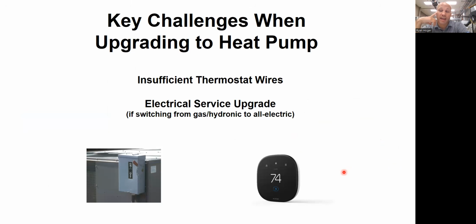But if it was a packaged rooftop unit with gas, I'm going to get rid of the gas and replace it with a heat pump that has electric auxiliary resistance heat. Now I probably am going to need an electrical upgrade, because the heat pump's probably fine. Instead of running the air conditioner, I'm running a heat pump. No big deal, right? But now I got this electric heater that I didn't have before. So now I need power for that.